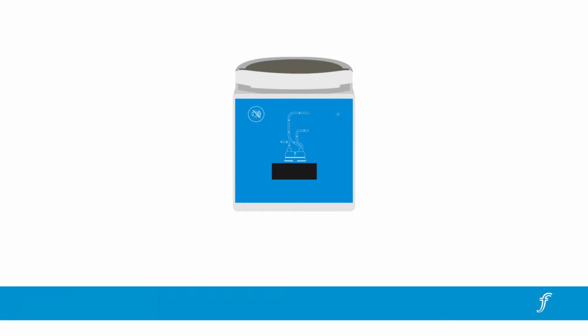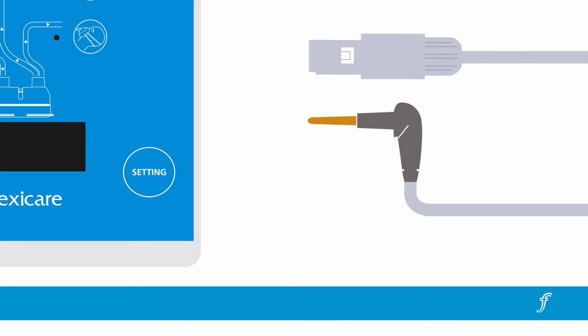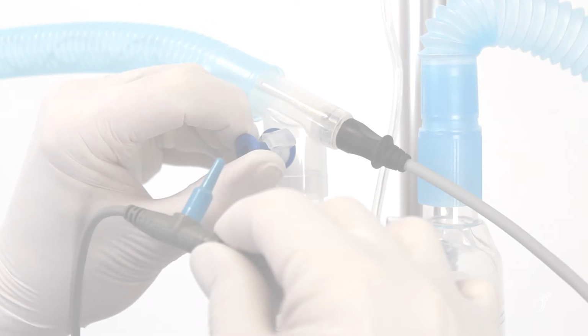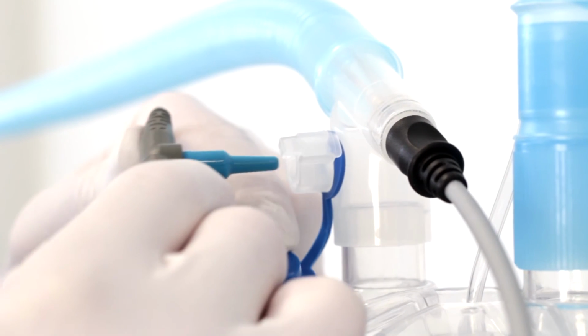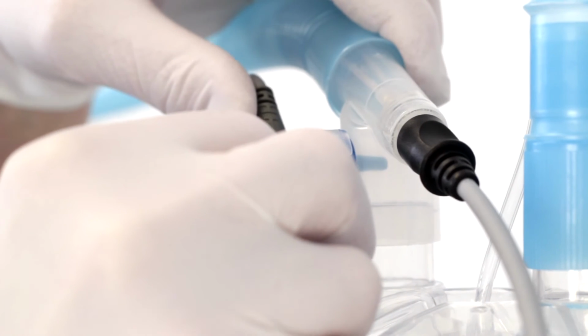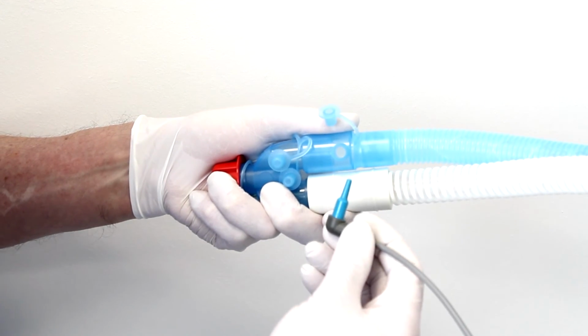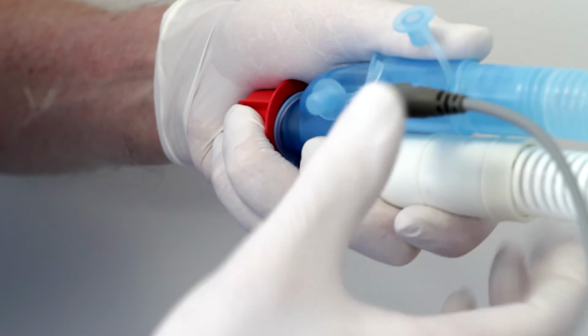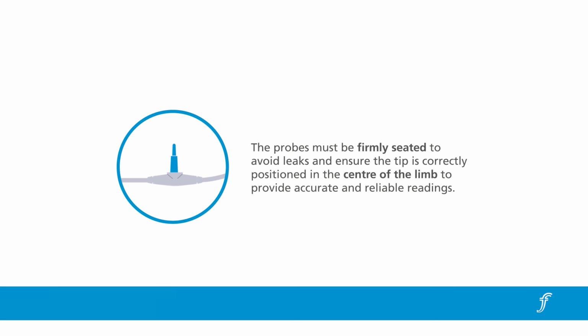The two different types of socket prevent attempted misconnection and potential costly damage to the heated wire and temperature probe leads. The central temperature probe is then inserted into the sensor port on the elbow of the inspiratory limb. The probe at the end of the lead is inserted into the sensor port at the patient end of the inspiratory limb. Please note that the probes must be firmly seated to avoid leaks and ensure the tip is correctly positioned in the center of the limb to provide accurate and reliable readings.